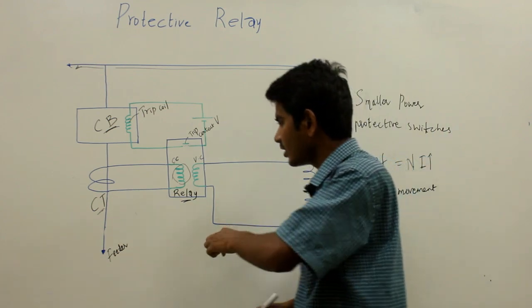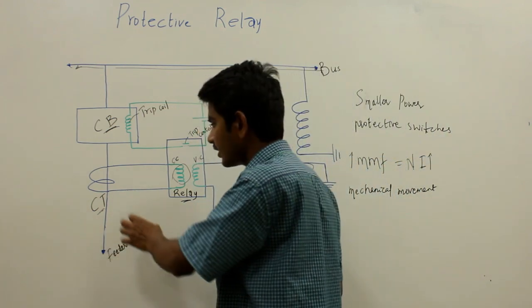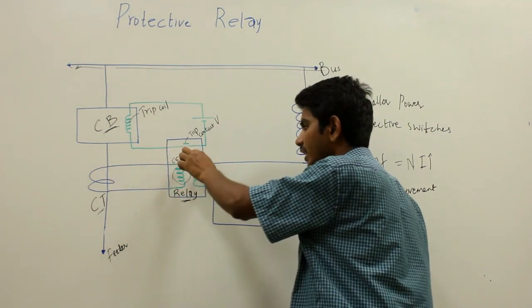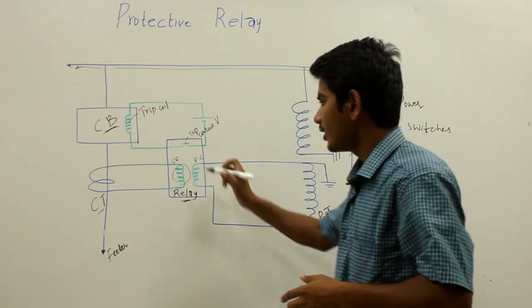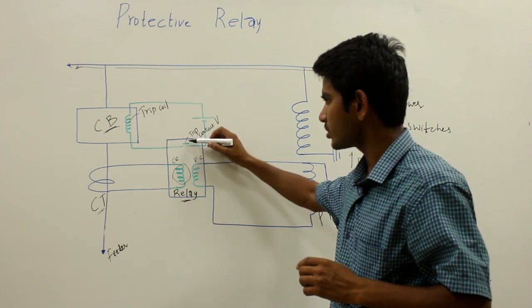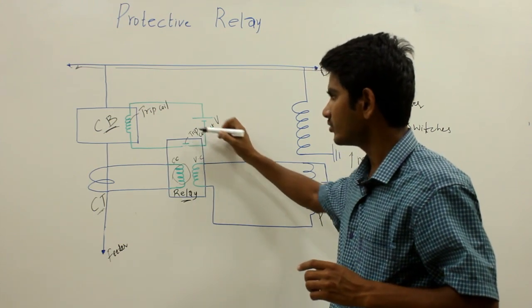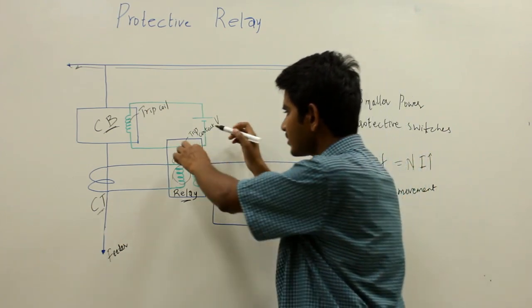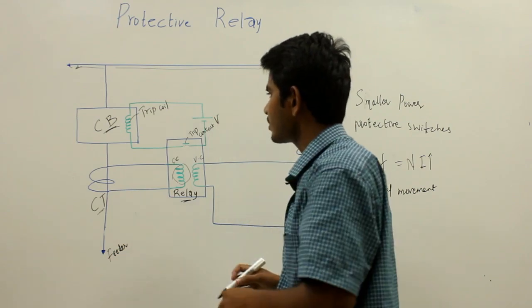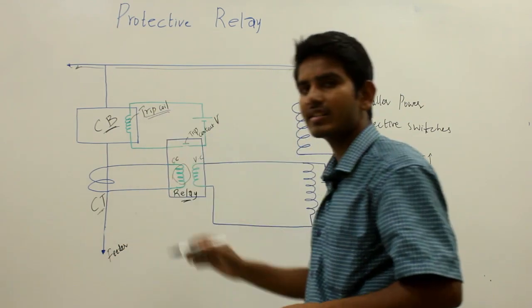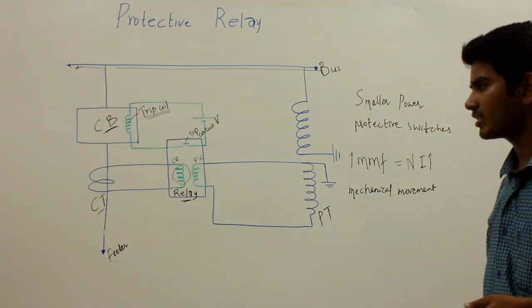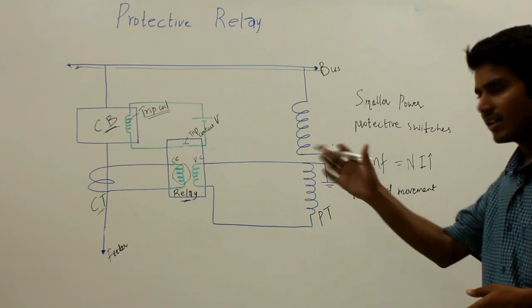To summarize: whenever there is a fault in the feeder circuit, the proportionate secondary current of the current transformer flows through the current coil of the relay. The high current causes the MMF of the current coil to increase, which is sufficient to close the open trip contact of the DC trip coil circuit. Once this contact closes, the trip coil is energized by the DC voltage, initiating the mechanical movement of the tripping mechanism, and ultimately the faulty portion is isolated via the circuit breakers.